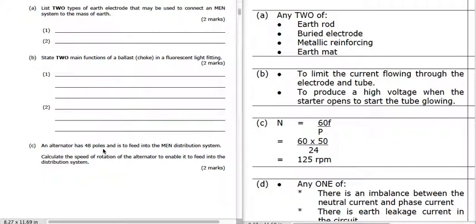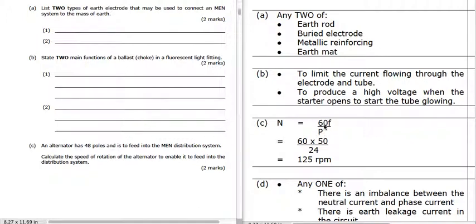An alternator has 48 poles. Whenever you see 48 poles or any amount of poles, in the formula P is going to be half of that value, because it's pairs of poles. It's fed into an MEN distribution system, and we're looking for the speed of rotation to enable it to feed into the system. We know it needs to be 50 Hz. Speed is 60F over P. Frequency is 50, P is 48 divided by 2, which is 24, and it gives us 125 revolutions per minute.